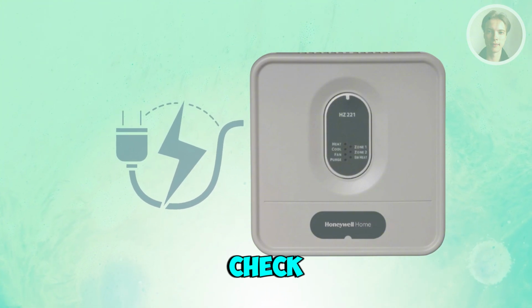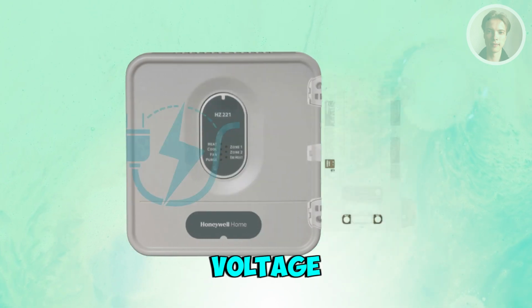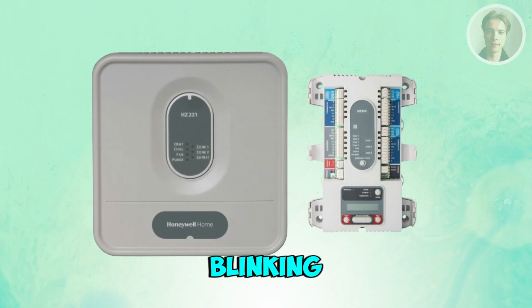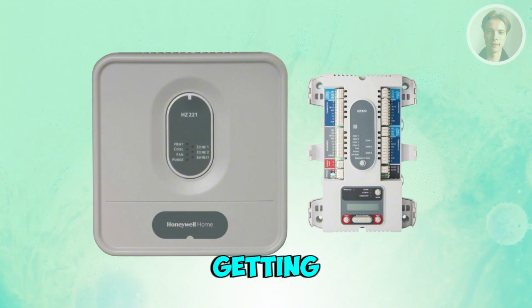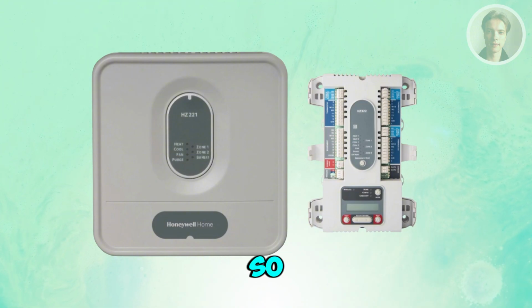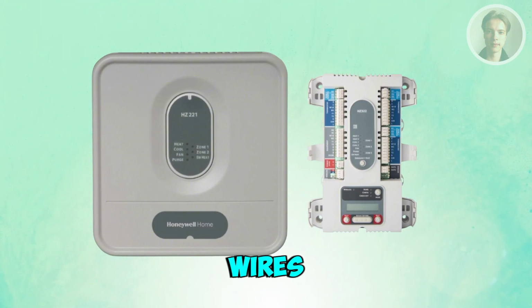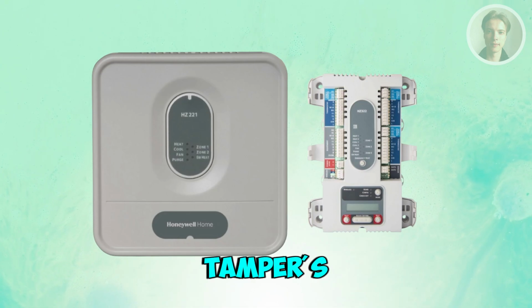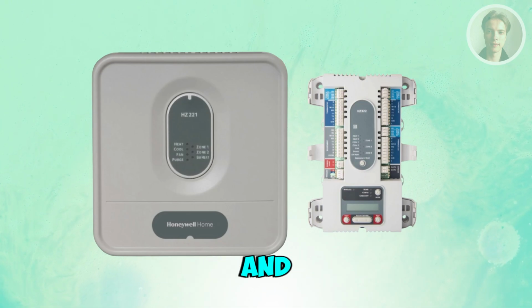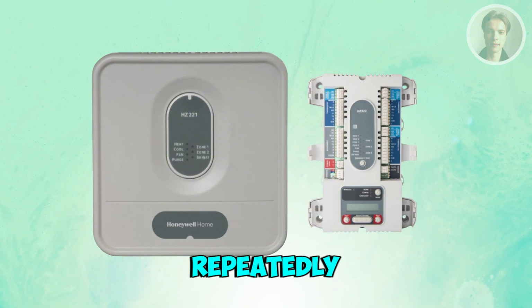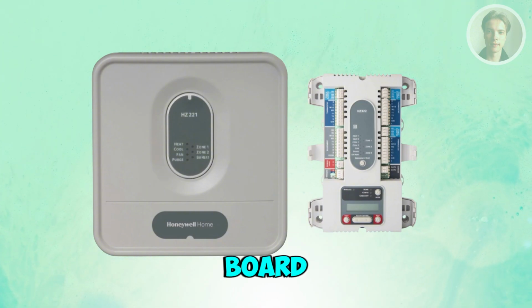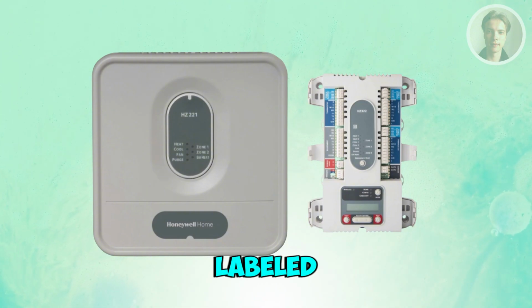Now, also you want to check the transformer and low voltage wiring here. Now, blinking on and off often happens if the panel isn't getting steady 24-volt power. So loose R and C wires, weak transformers, or overloaded dampers can cause voltage drops and make the panel restart repeatedly. Now, look closely at the HVAC control board wiring with R and C labeled.